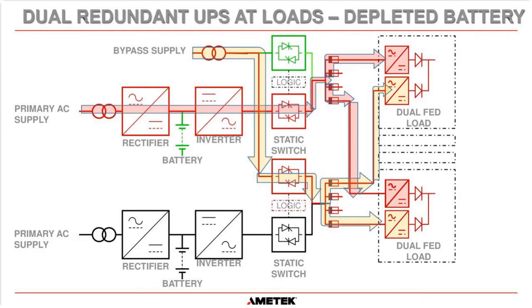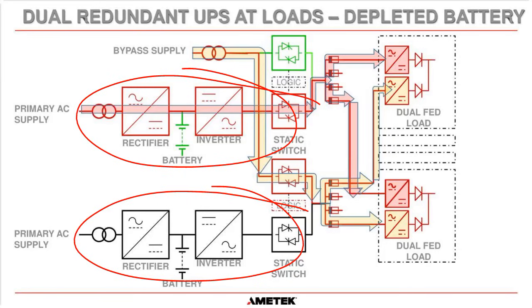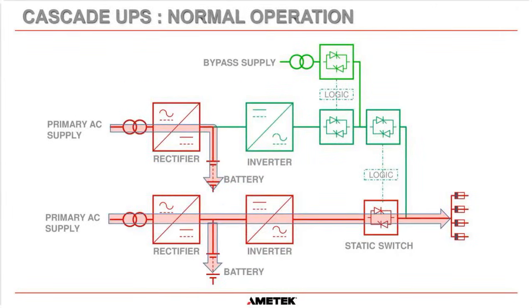And similarly, if I go back to this slide here, this UPS could be one manufacturer, and this UPS could be a different manufacturer when you are paralleling the systems at the loads. As long as they are rated the same, this has to be 30 kVA if it's a 30 kVA system, and that has to be 30 kVA. In theory, I don't know why you would do it, you can have one manufacturer for that UPS and a different manufacturer for that UPS. That is the same with a Cascade, because they're not connected in parallel and there's no electronics between the two systems. UPS B could be one manufacturer and UPS A could be a different manufacturer, as long as they are rated the same.